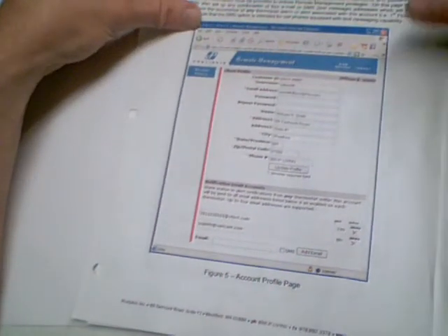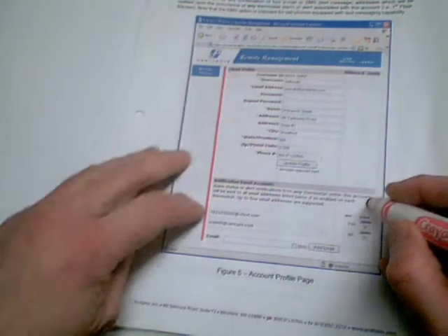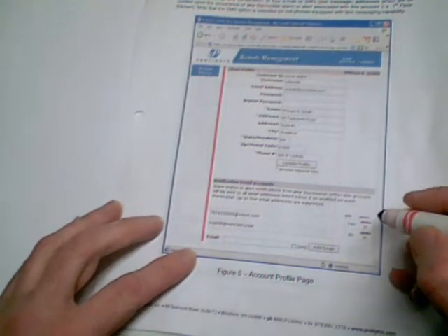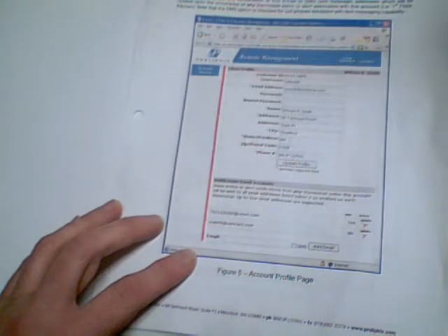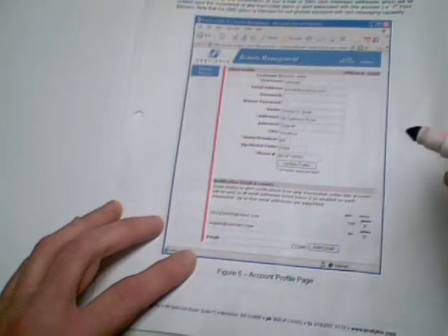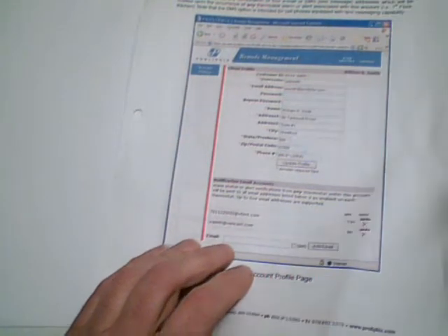When you go to set it up, you give it your customer ID and all this kind of stuff. And then you set up notification email accounts down here, or mobile phones. And you can just put in either your email address, of course, or you can put an SMS in for your cell phone and have it text message you when there is an alert that has been set. So it's either going to be the high temp, the low temp, the filter needs changing, or it can't reach it because it didn't call home within that 1 hour discovery period where it needs to call home to the mothership each time. If it didn't do that, then it tells you that it can't be reached.